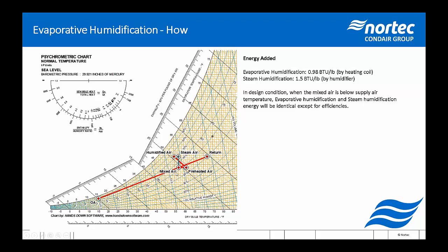So in this case, when we reach that point, we've got an air that's approximately the right temperature because we're in heating mode, but we still need to add the humidification. Because we've mixed our 40% return air with our, yes, it's 90% RH outside air, but it's a very low water capacity down there. So we've mixed up and we've hit somewhere around 56 degrees and 52%. But in order to reach the return air or the room air set point, we need to add a few grains per pound of dry air. A few thousand. And to do that, we have to boil the water.